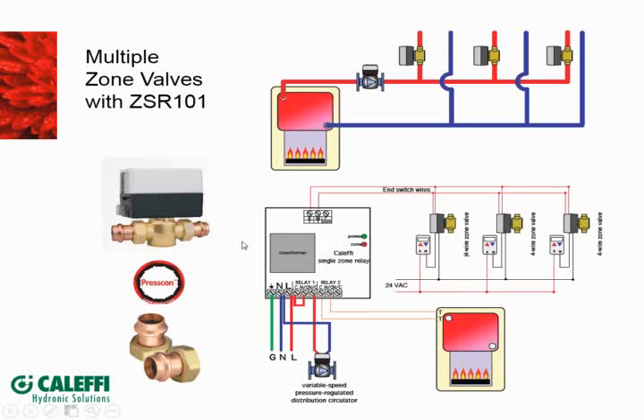And I'm not sure what the intention of this one is. I guess just instead of buying a 3-relay board, to save some money. Yeah, it's a poor man's relay. I don't mean to use that term in a bad way, but that's what it is. It's somebody that didn't want to spend the money on the 3-zone valve controller, said, well, I'll just buy a single one to do my switching and then use another source for my power. Sometimes the boiler has enough transformer in it to power those, if it's an older type of boiler.